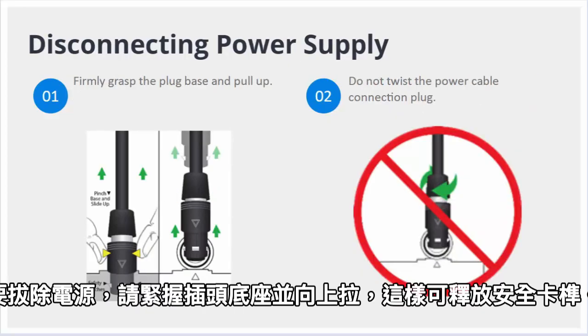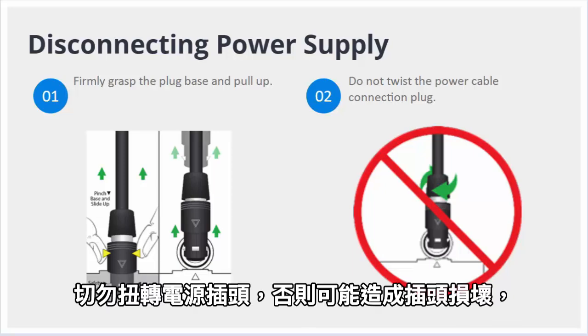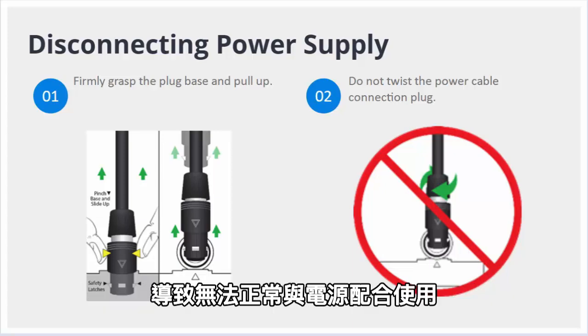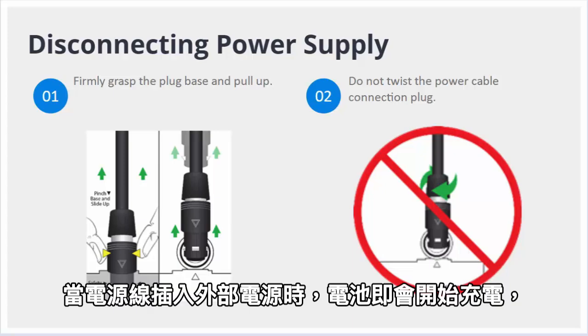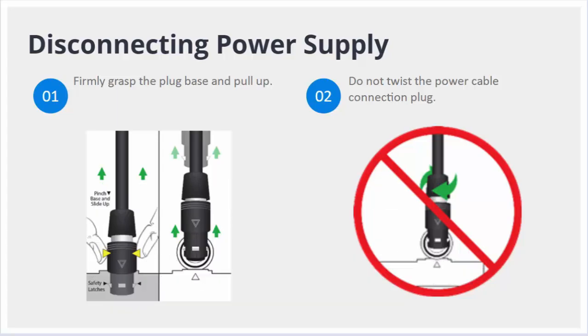To disconnect, firmly grasp the plug base and pull up. This releases the safety latches, allowing cable removal. Do not twist the power cable connection plug. Failure to do so may damage the power connection plug and prevent it from functioning. With the power supply cord plugged into external power, the battery is charging. This is indicated on the user interface in the icon area of the aspirator screen.